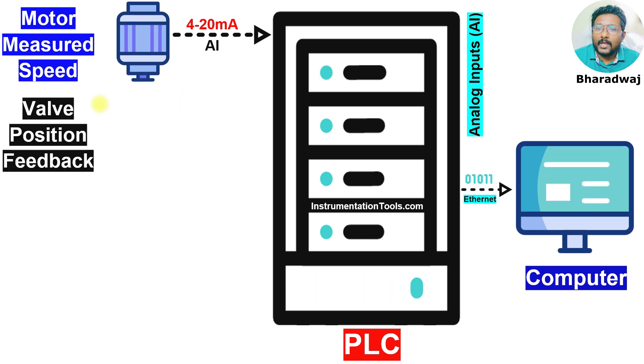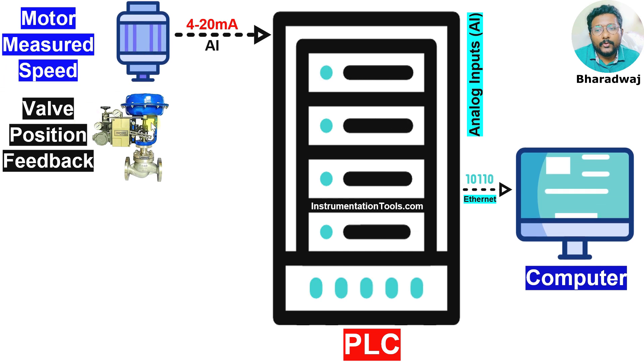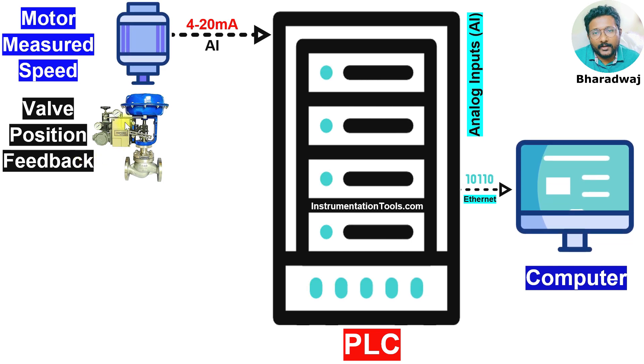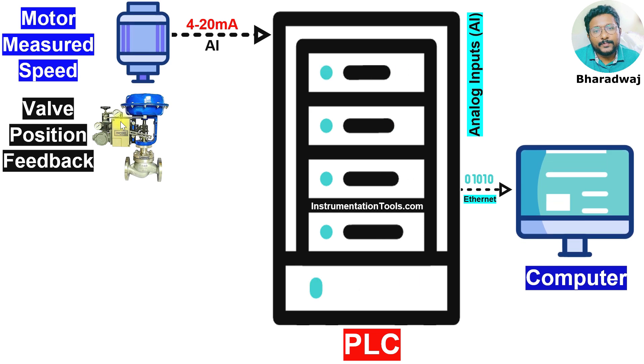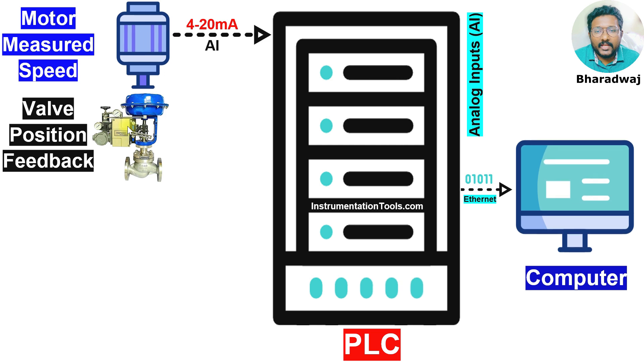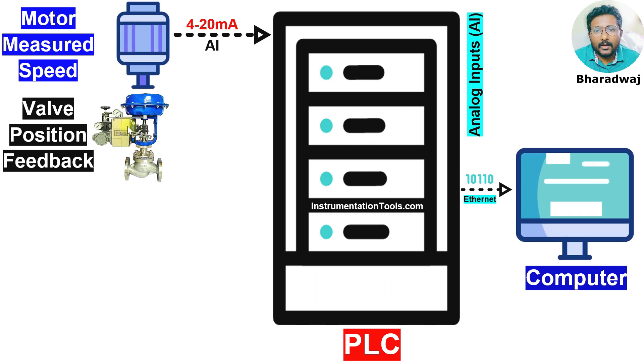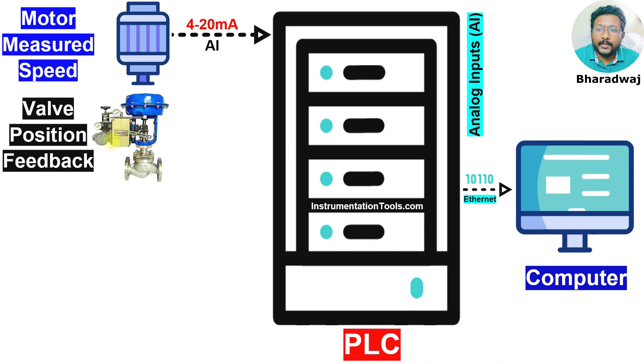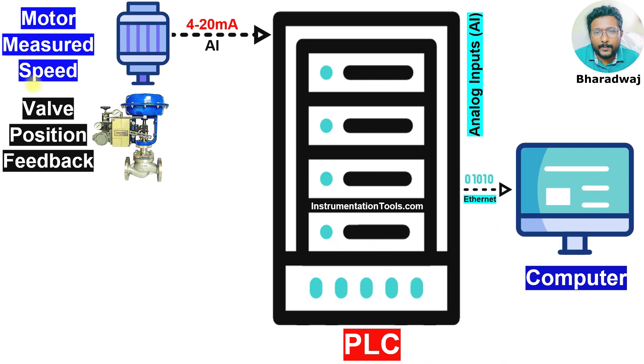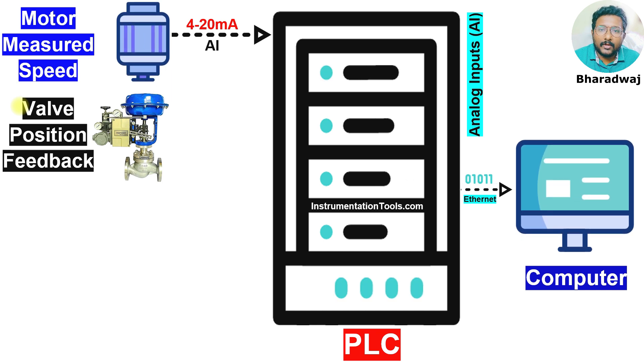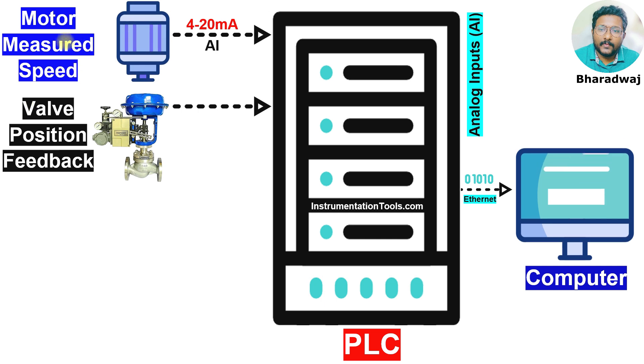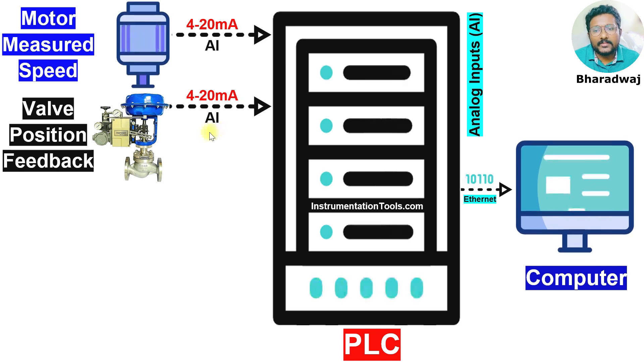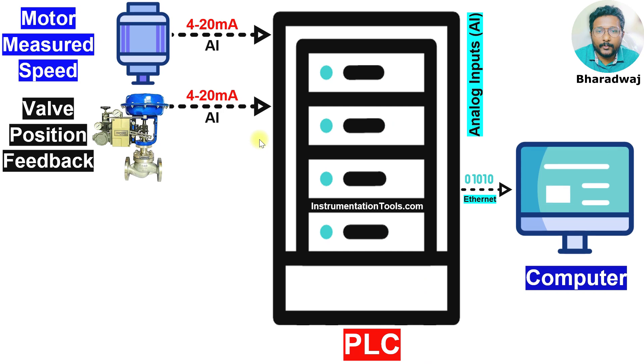If you have a control valve, you can take valve position feedback — that means how much the valve is opened. For example, 26% the valve is opened, 70% the valve is opened, or 40% the valve is closed. You can take the control valve feedback. This feedback is an analog input to the PLC — a 4 to 20 mA analog signal, analog input.